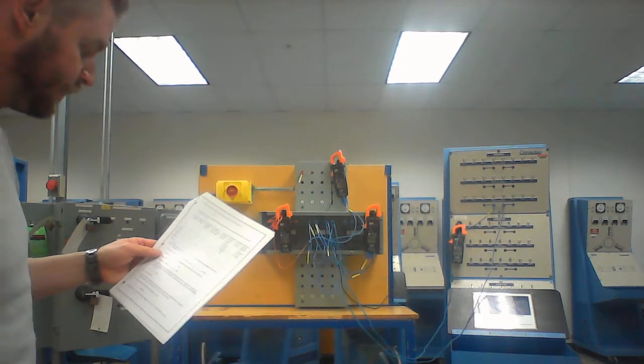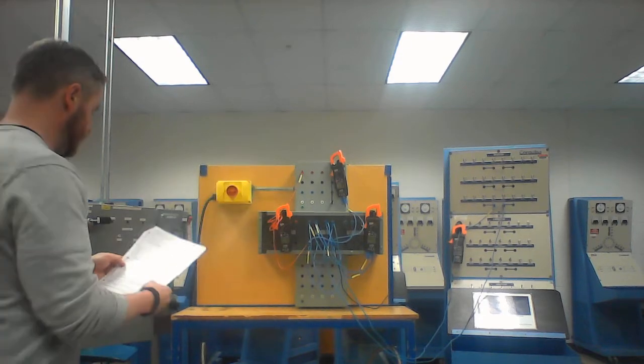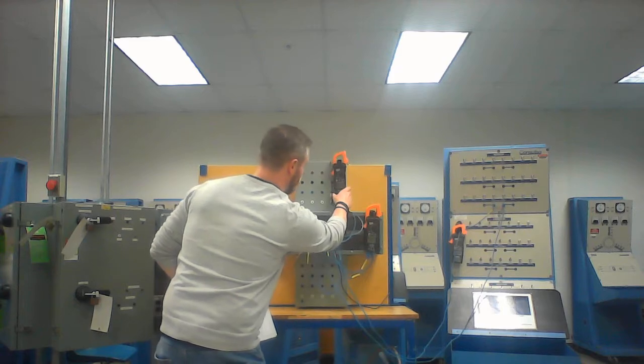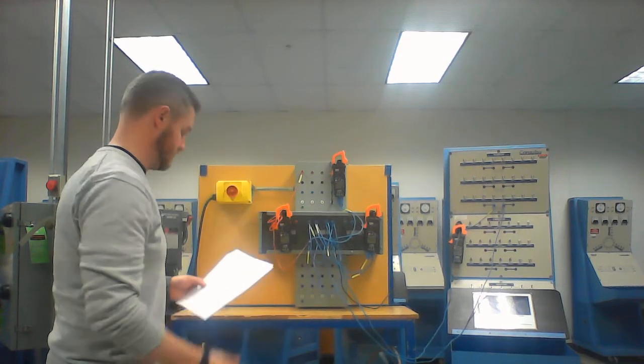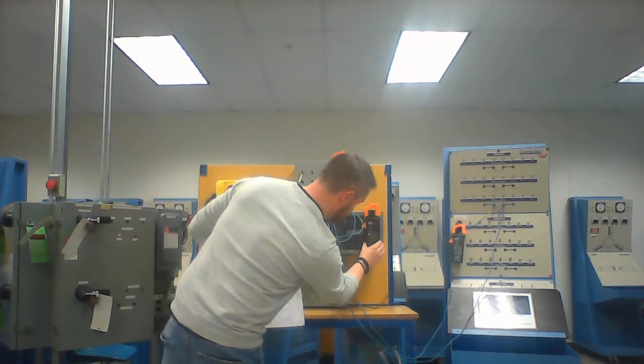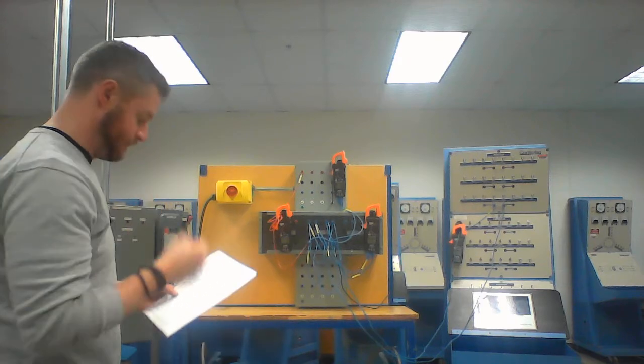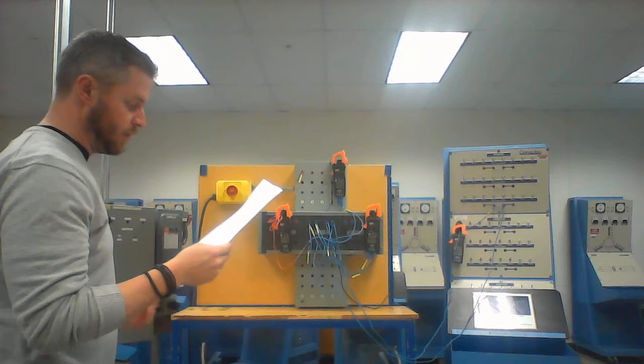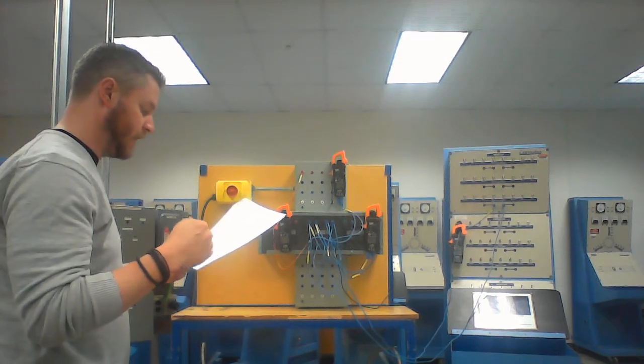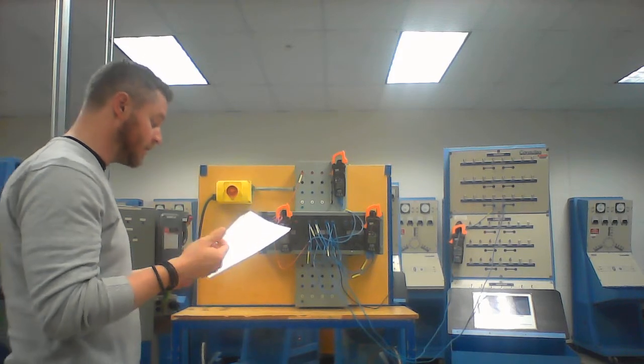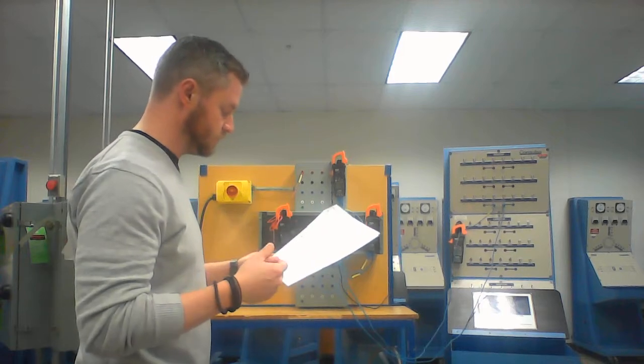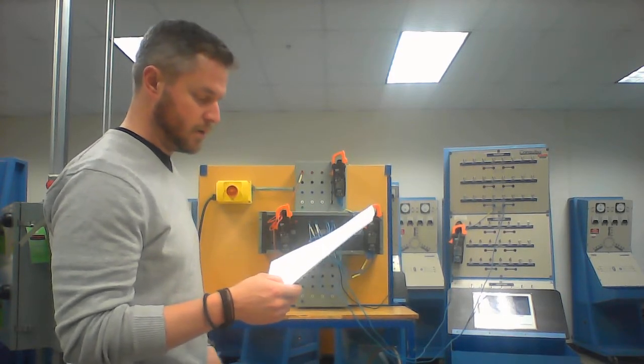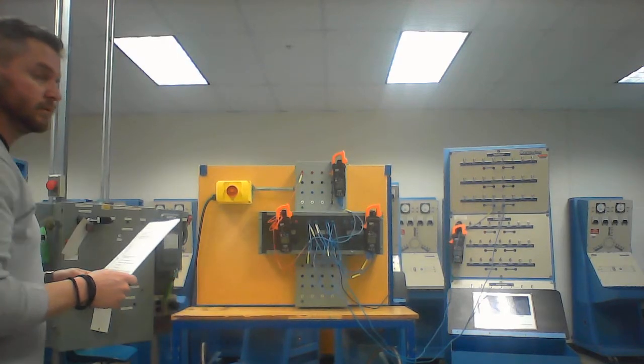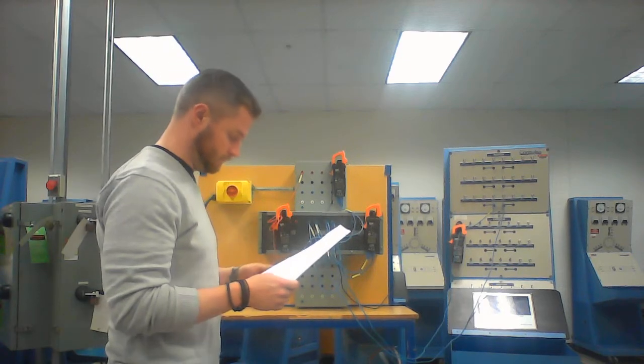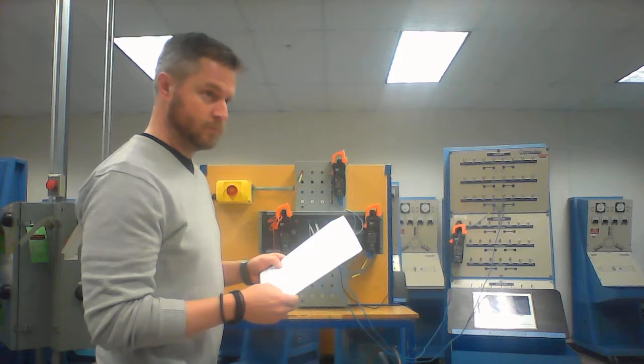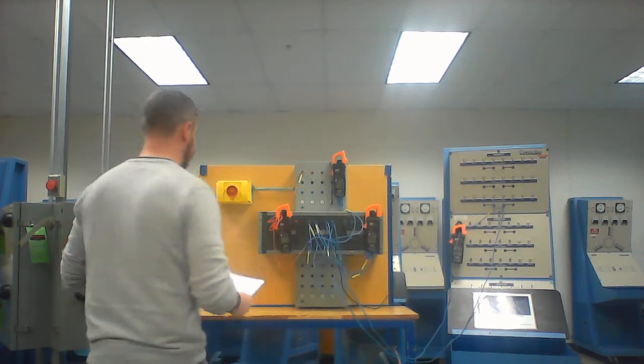Then step 14 says measure the voltages on the low voltage and high voltage sides of the transformer. Your low voltage side, I am reading 117.8, and my high voltage side, which is my secondary, 192.2. So we'll determine the voltage ratio by dividing the high voltage by the low voltage. Since the primary voltage, the low voltage side, is lower, the larger number will be placed on the right hand side of the ratio. And if we do that calculation, 1 to 1.63. Perfect. Okay, turn the power off.